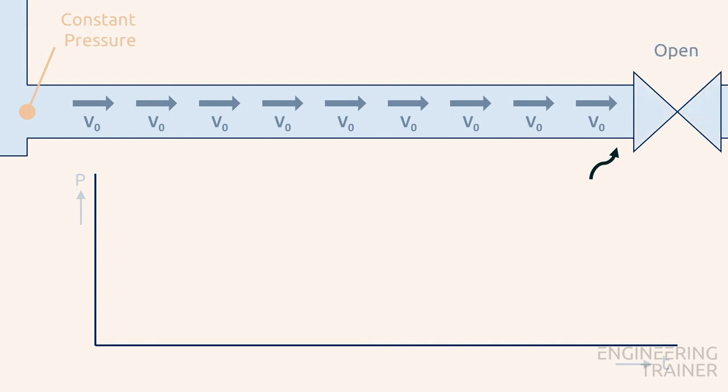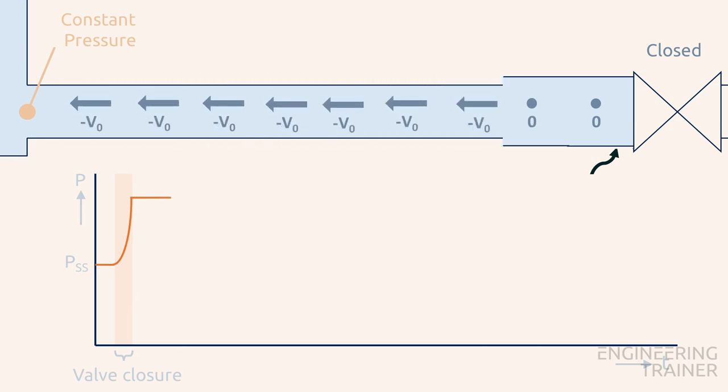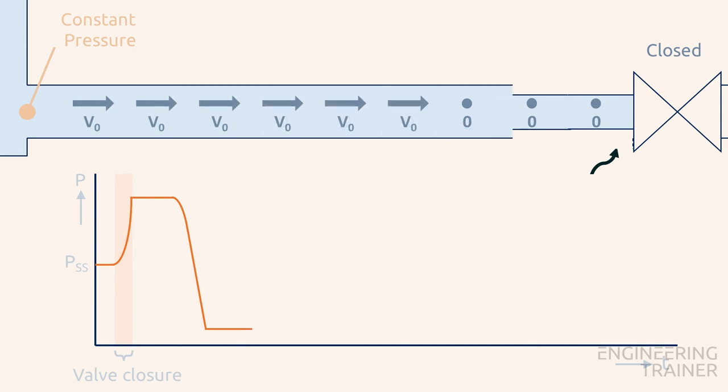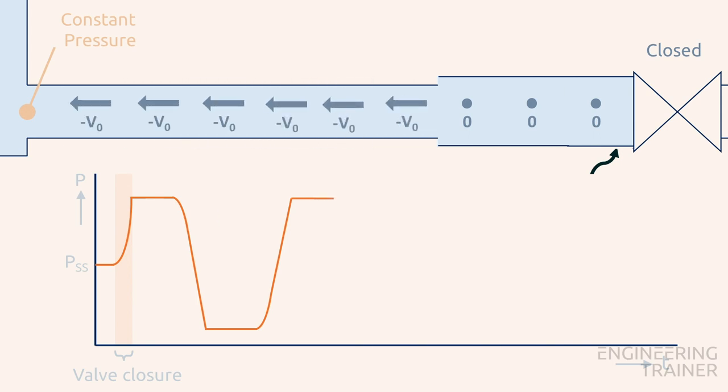During steady state operation the pressure has a constant value. When the valve is closed the pressure increases and stays more or less constant as the compression wave runs upstream. Once the wavefront returns to this location the pressure decreases again. But now the momentum of the flowing water pulls on the water close to the valve, thereby creating a pressure drop which goes below the original steady state pressure value. Again this value stays more or less constant as the waves are running through the system. A new pressure peak is created as the loop starts over again, and this pattern continues over time.